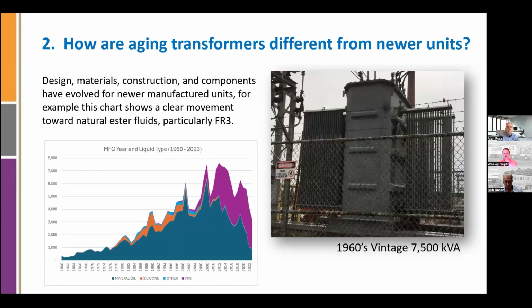And then one last idea to set the scene for how aging units are different than newer units. I wanted to present how components change over time. So one component, if you will, of a transformer is the liquid that fills the main tank. It covers the core and coils, providing an extra layer of heat distribution. And the chart on the bottom left here shows across manufacturing years. So on the x-axis, we're going to start in 1960. We're going to go all the way up to 2023. The dark blue shows the presence and the prevalence of mineral oil in transformers.